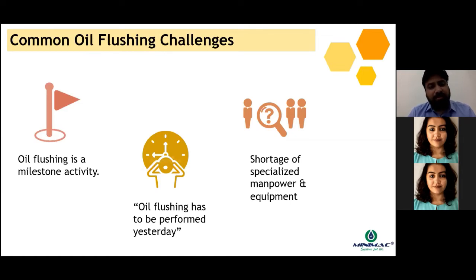Many times the oil flushing activities take a longer time because the pipeline contractor had not welded or fabricated the pipeline in a good fashion. A lot of times it is because the chemical cleaning contractor had not done his job in a proper fashion. So oil flushing, although it is the last milestone in the pursuit of preparing your system for commissioning, is one of the most important and the last check activity in your pre-commissioning schedule of activities and tasks. So as it's a milestone activity, you might always face a sudden rush around it, but it's important for us as technocrats to understand that oil flushing cannot happen in a rush situation, but can happen only if it is performed in a well planned fashion.